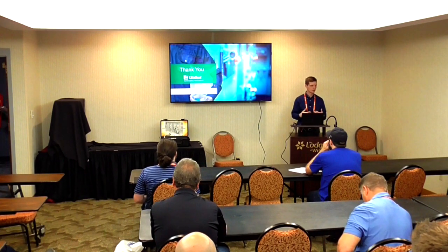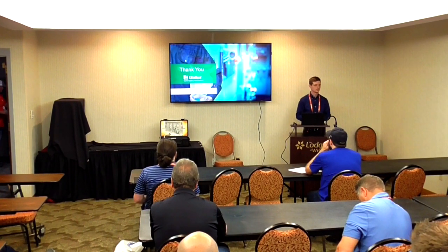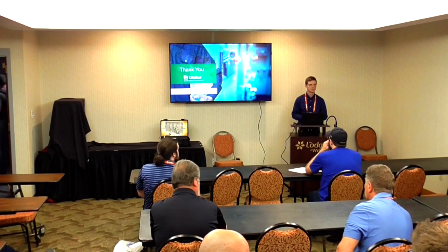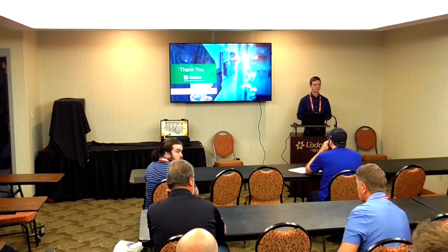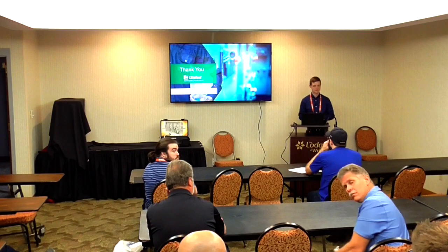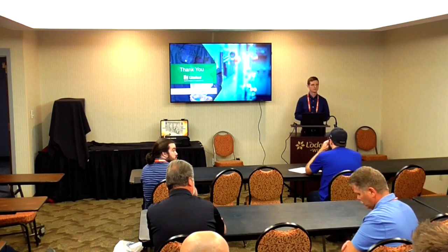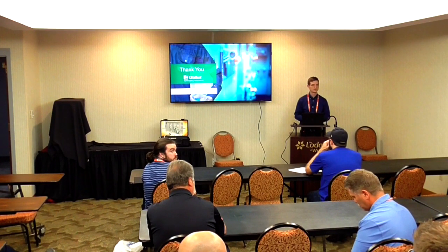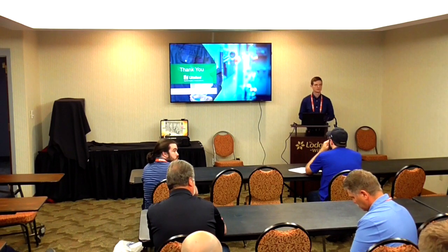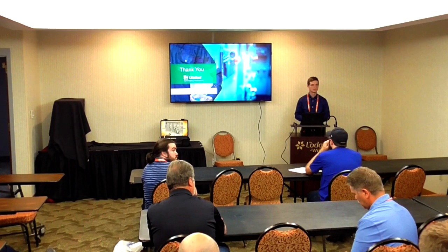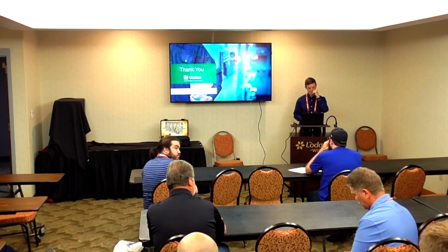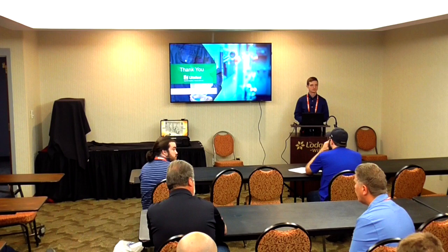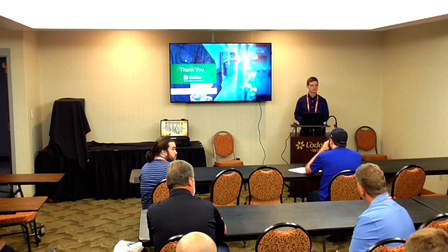And if they have questions, they can reach out to us and my team here, and we can walk them through it. Hey Josh, if I can interject, if anybody has one line of category 3, 4 dangerous, send that to any of the CD Mosbach guys, and we can model that for you by putting this relay in there. And then typically we come out into the field and help do that installation, and we'll do the point placement with you. We're not electricians, we're just the manufacturer's rep, but we'll help you and say, don't put that here or put this up above, and direct on where that goes the first time. But the main thing is, if you have a category 3, 4 dangerous, get the modeling done and ask how can we reduce this hazard? And if you can get that down to a category 1 or 2, why wouldn't you do it? That's the biggest takeaway from this whole session.